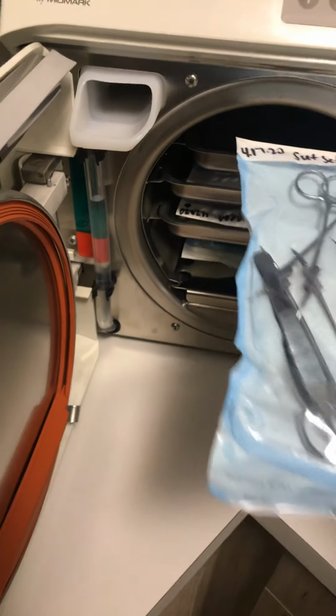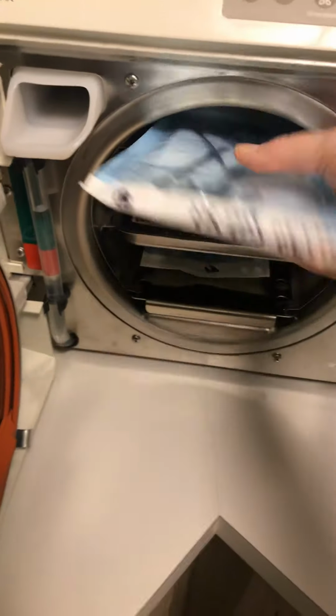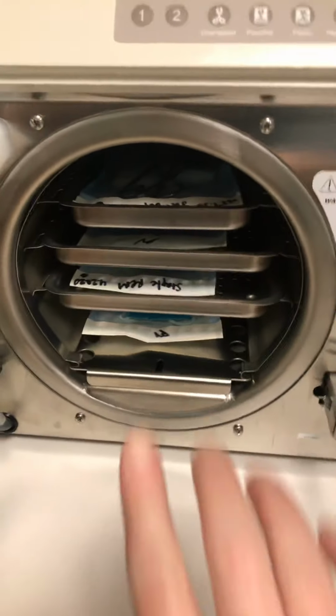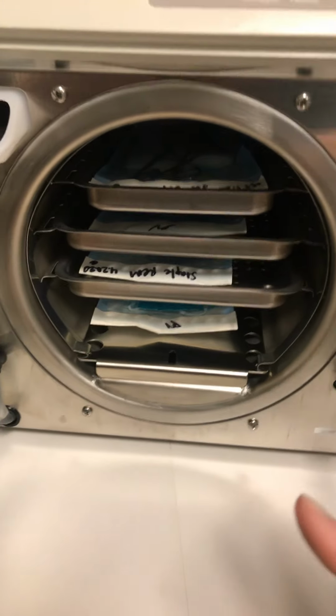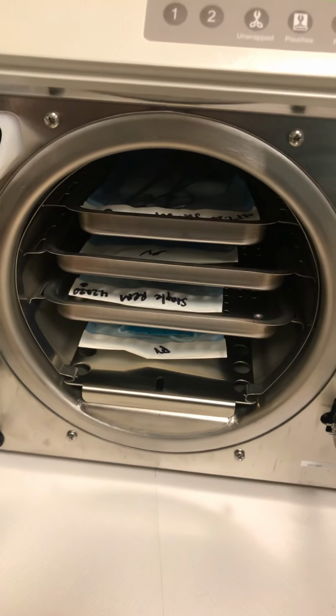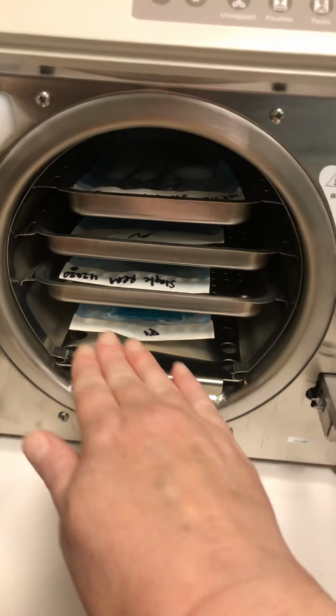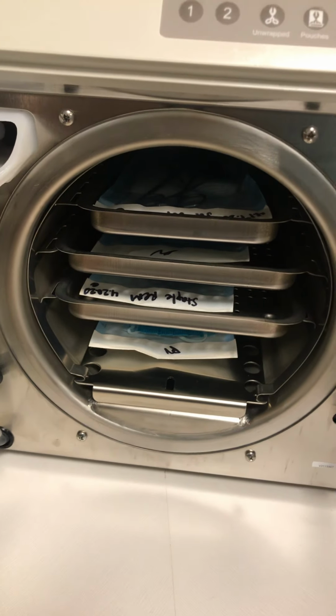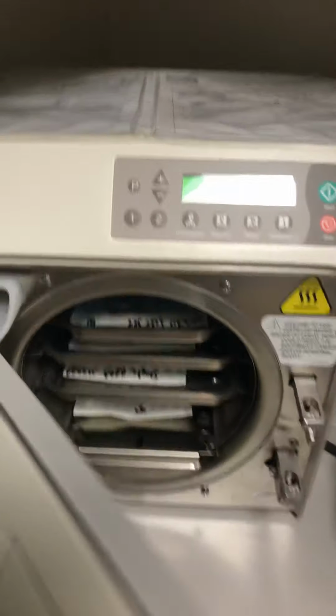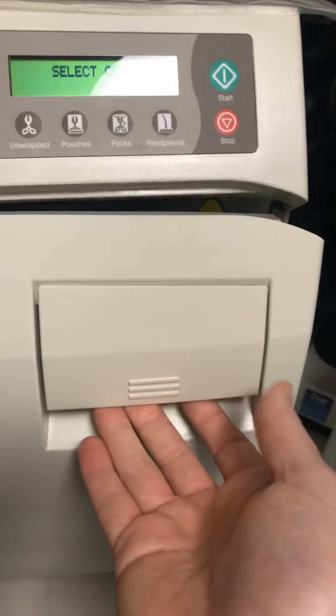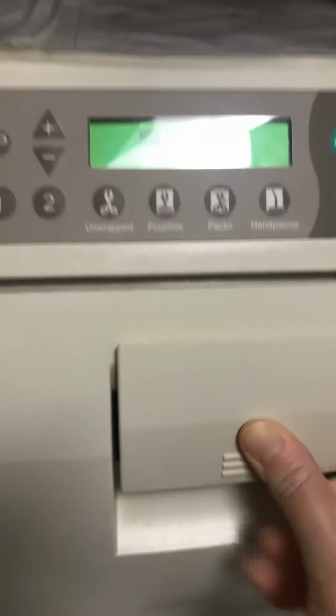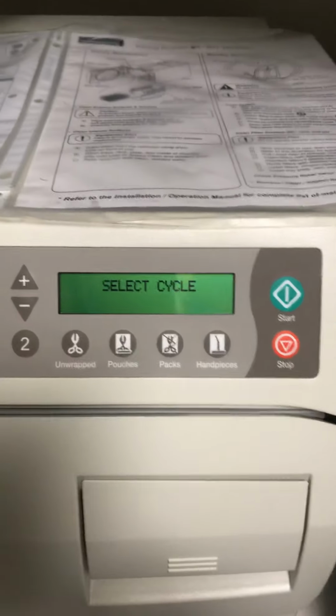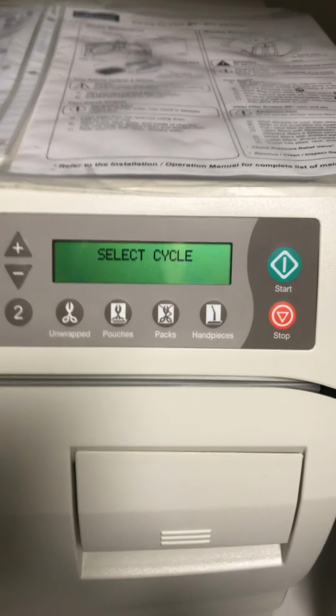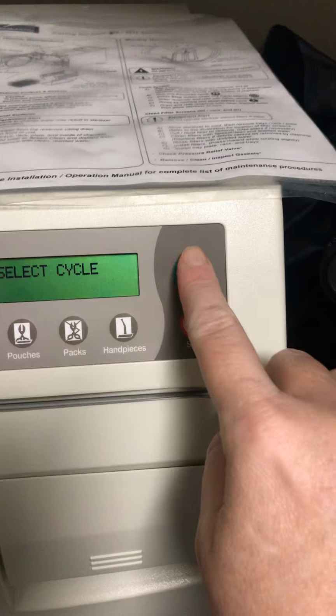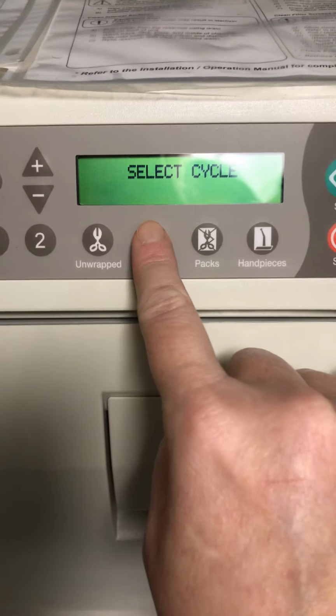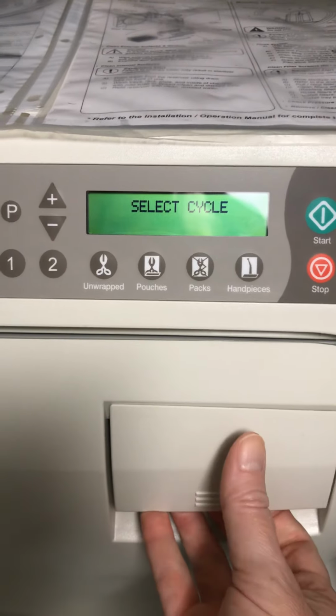And then if these pouches hadn't been sterilized, right? So you would stick them in. We stick them in on the different shelves. So they have to be kind of 1 inch apart because the steam has to get around all the instruments and sterilize them. So you have to put them in on those individual shelves. And you simply shut the door. And right here, the handle, you always pull it up, push it down. And on the cycle, you simply press the start button right here and the pouches button. And that's it to start running your cycle.